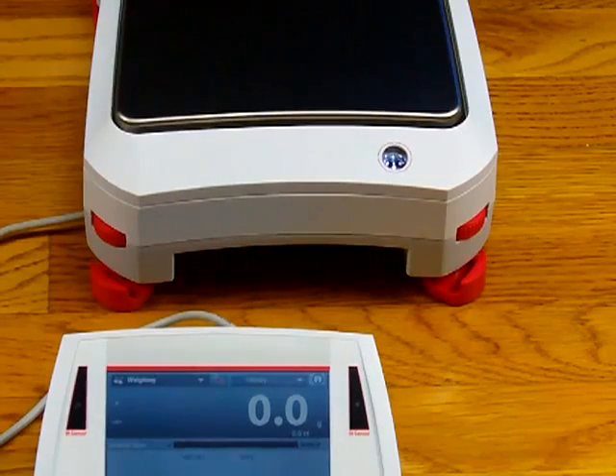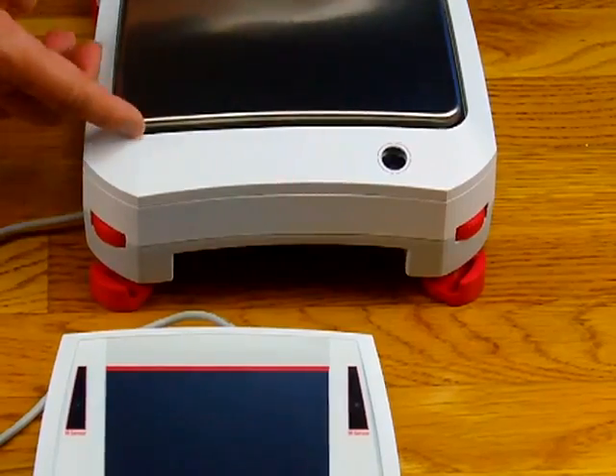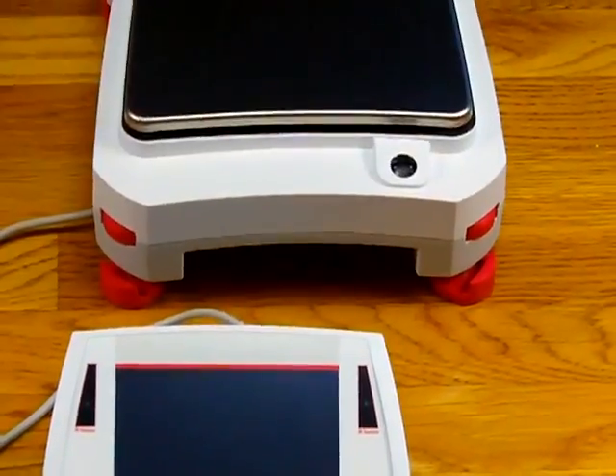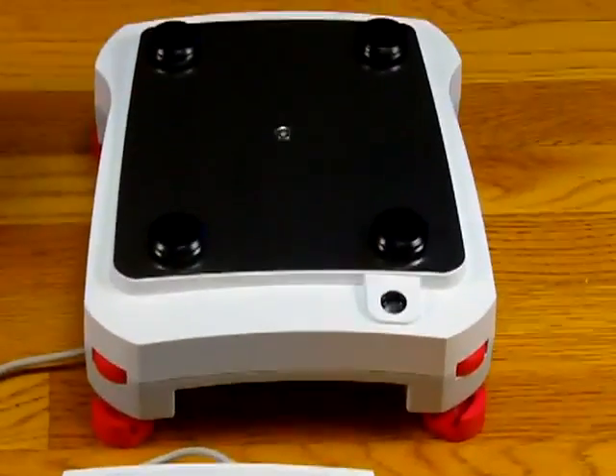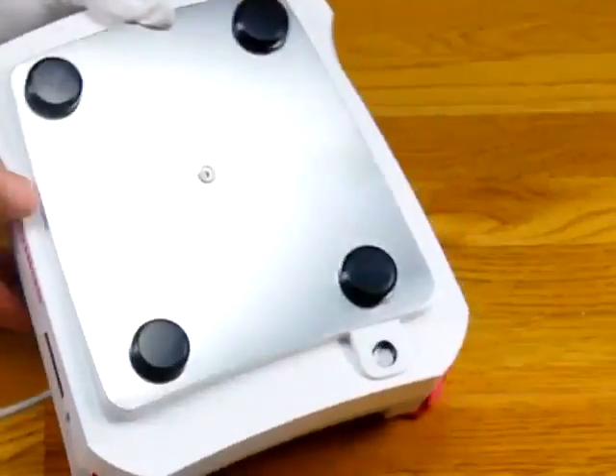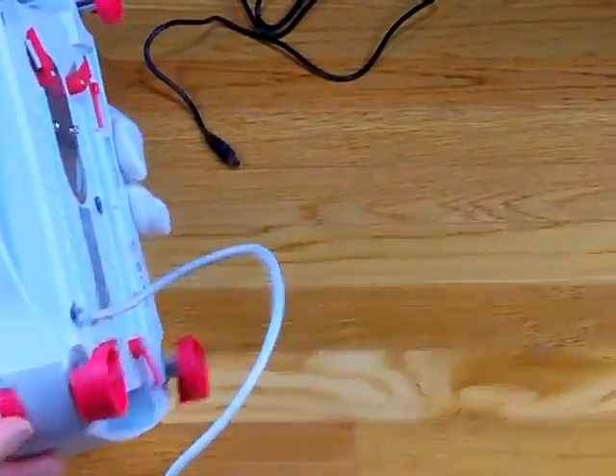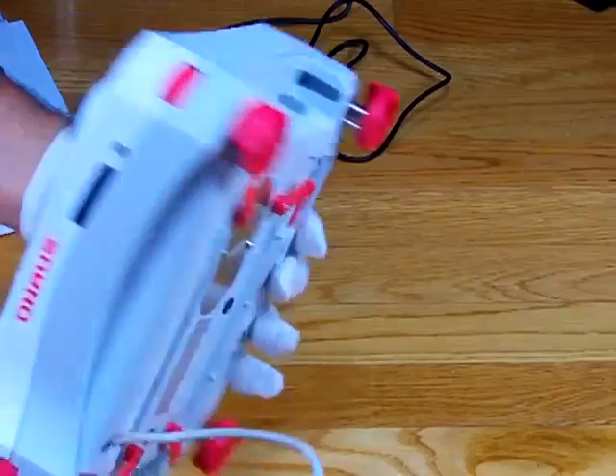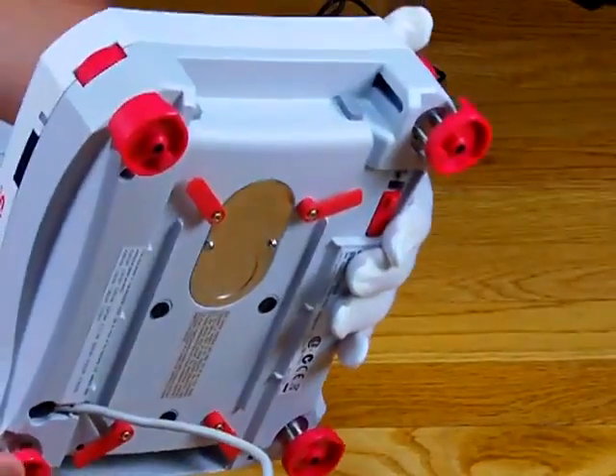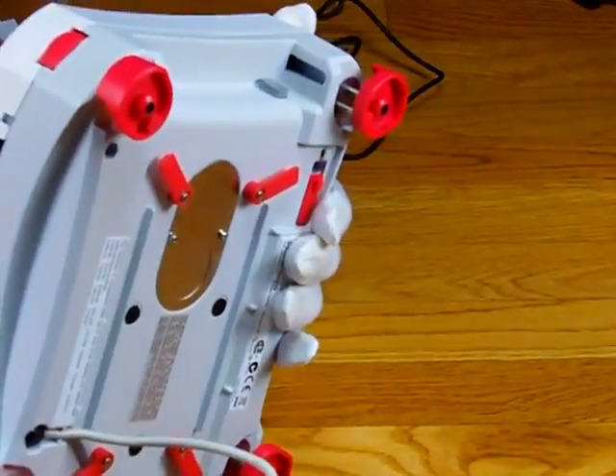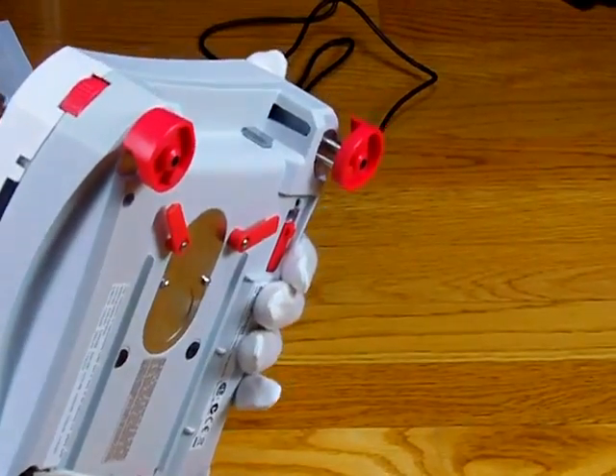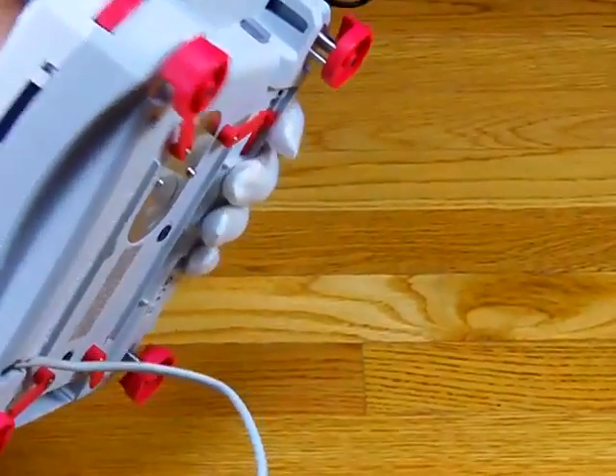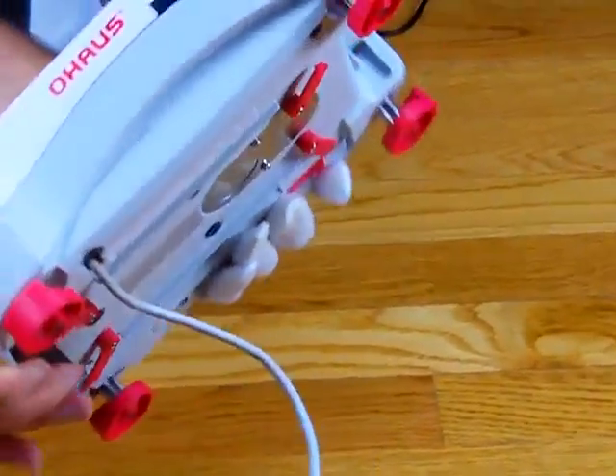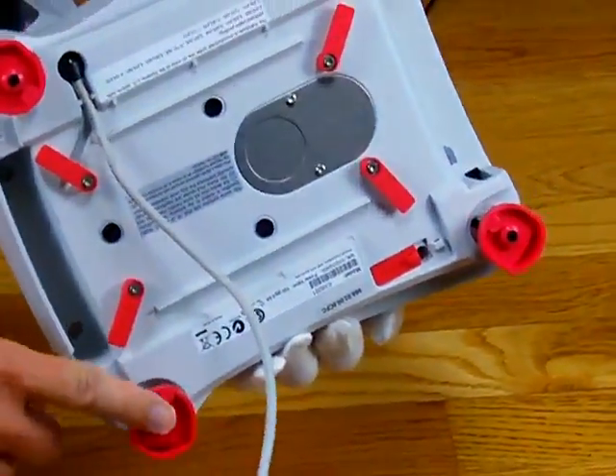The balance has 4 adjustable feet. I'm going to unplug the balance for a minute to show you these features. The balance has a menu that helps the operator decide which foot needs to go up or down. On the bottom, you'll see the 4 adjustable feet, which are high quality. There's a post with another support on the other side, and the operator just turns a little wheel to adjust the balance. So calibration and leveling the balance is very simple, with 4 adjustable feet.